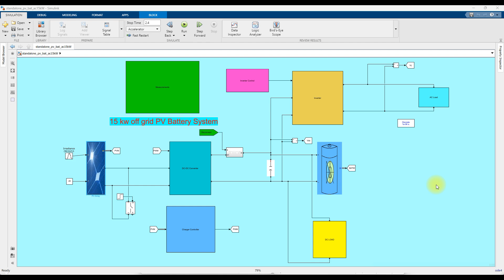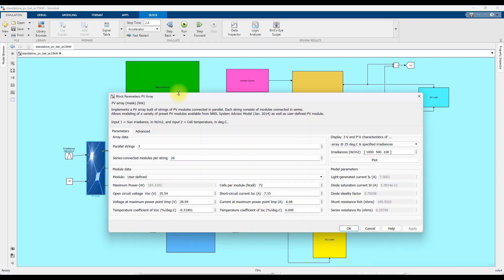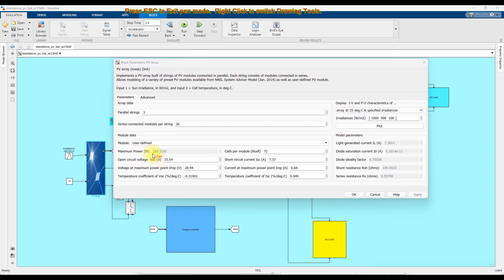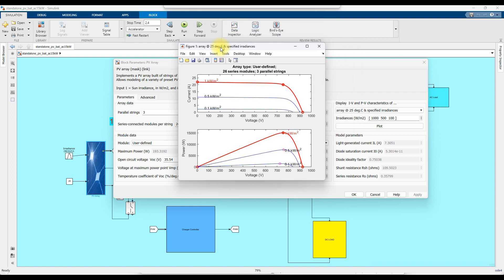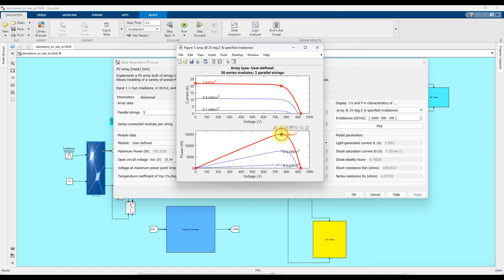This is a simulation model developed for a 15kW off-grid PV battery system. The system consists of a PV array. The single PV array power rating is 193 watts, voltage is 28.94 volts, and current is 6.68 amps. A single string has 26 panels in series and the total parallel strings considered here is 3. You can see the IV and PV characteristics of the PV array at 1000 watts per meter square — the power generation is around 15.08 kilowatts and the voltage is 752.4 volts.